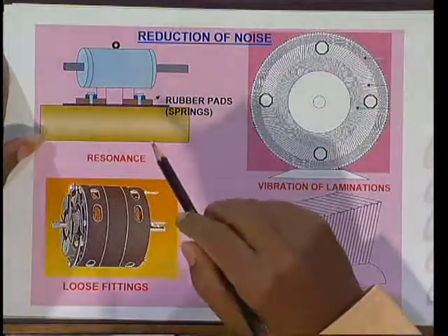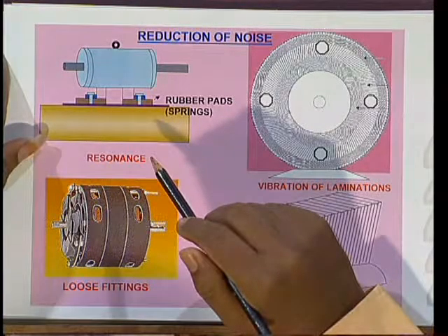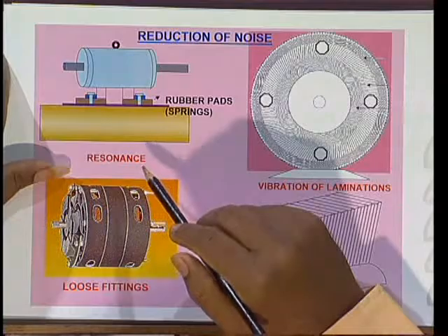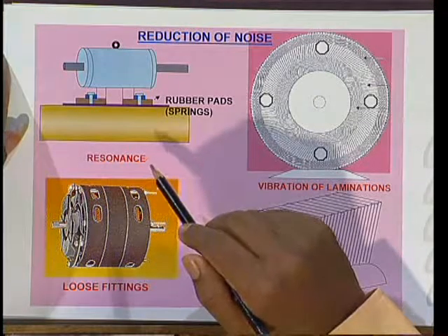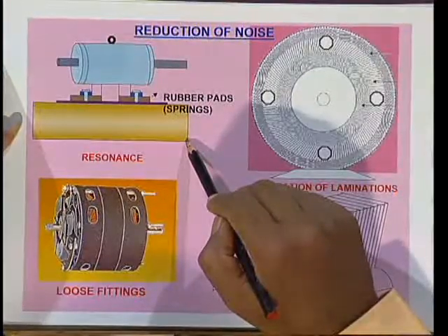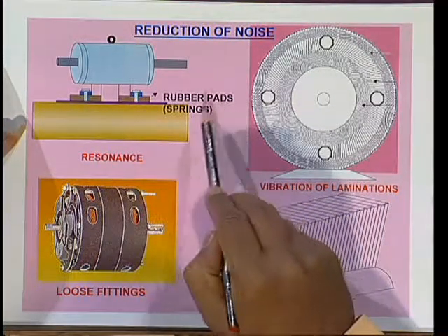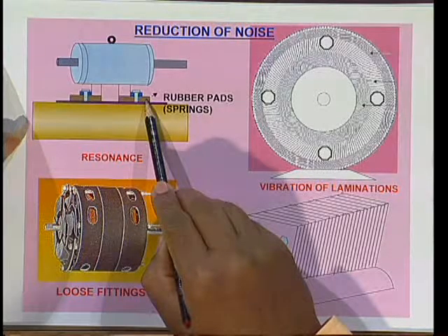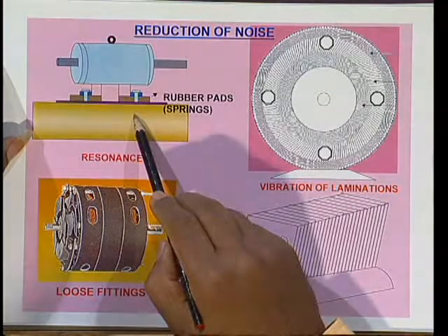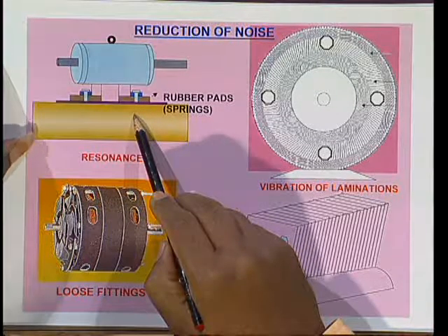Now let us see the conclusion: what are the main reasons for production of noise in a motor, and how we can reduce this noise. Noise may be due to resonance or mechanical vibrations. This can be avoided by using a flexible foundation — that means by providing rubber pads or springs at the bottom, you can reduce the mechanical vibrations. Noise may also be due to vibration of laminations.